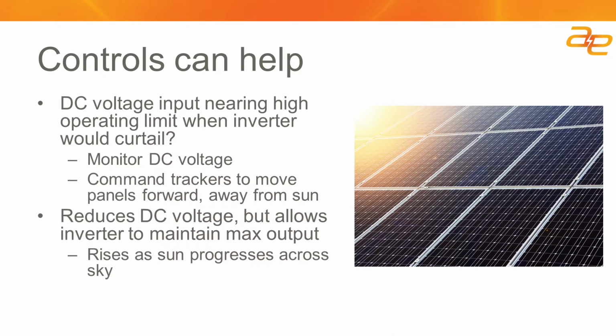And controls can definitely help. So if you've got a tracker system, your DC voltage going into the inverter is a parameter that we monitor from SCADA and can integrate with controls. If we see that the DC voltage is getting high, we can command the trackers to move a little bit ahead of the sun, which would reduce the DC voltage and bring it back into range. So your inverter output remains the same, and you're using the ability of the trackers to manage your DC voltage going into the inverters. Again, today with most inverters that I see, this isn't really a big concern, but with some less expensive inverters, it might be an opportunity for you to keep the DC-AC ratio high and keep the inverter output running when it might otherwise trip.